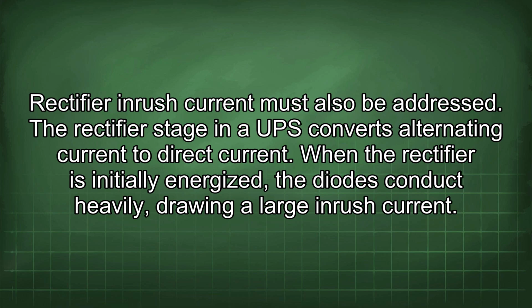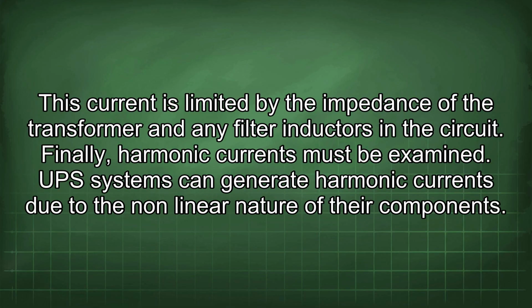The rectifier stage in a UPS converts alternating current to direct current. When the rectifier is initially energized, the diodes conduct heavily, drawing a large inrush current. This current is limited by the impedance of the transformer and any filter inductors in the circuit. Finally, harmonic currents must be examined.